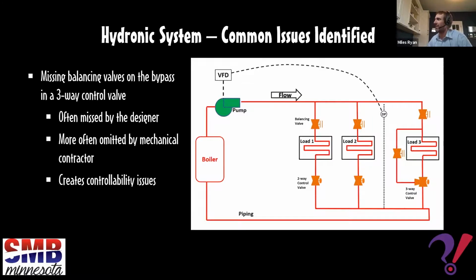So if you're a design engineer, don't forget the balancing valve in the bypass. If you're a contractor, even if the design doesn't call for it, put in an RFI. There should be a balancing valve in the bypass. And if you're a TAB or commissioning provider, look out for that, because it might be a reason your system's not operating the way you expect it to. All right.